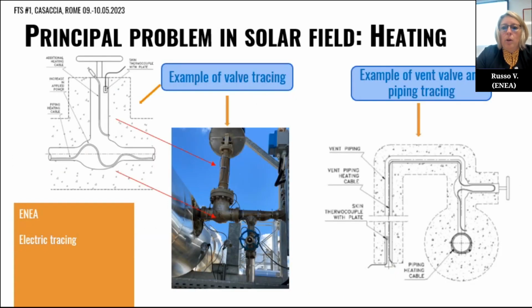Here we can see another example of correct tracing installation, especially on a valve. In this case, we have to install two electric cables, one on the body of the valve and another one on the bonnet of the valve. As a consequence, we also have to install two thermocouples for the control of the temperature. Generally, the thermocouple is positioned on the bonnet because the bonnet is the coldest part of the valve. In this way, we can assure the movement of the valve at all times.